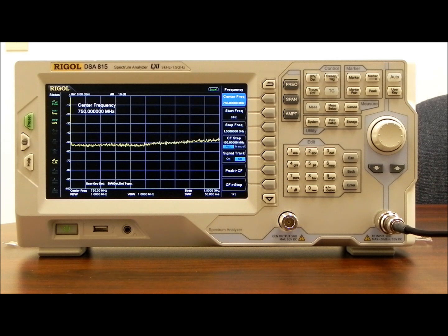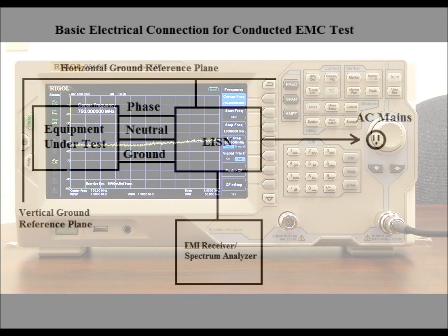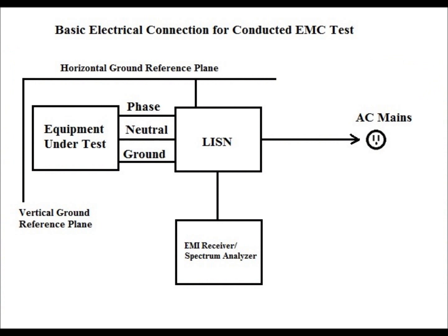I'm going to be stepping through a lot of the procedures with one of our spectrum analyzers, the DSA 815. I also am using some other instrumentation. In this slide you can see the equipment under test, with the phase, neutral, and ground connected through the power cord to the LISN. We also have the horizontal ground reference plane and vertical ground reference plane — conductors bonded together that are at least two times the area of the equipment under test, which helps isolate the EUT from capacitive coupling to anything in the room. The LISN is also connected through the AC mains as well as to the EMI receiver or spectrum analyzer — in this case, the DSA 815.